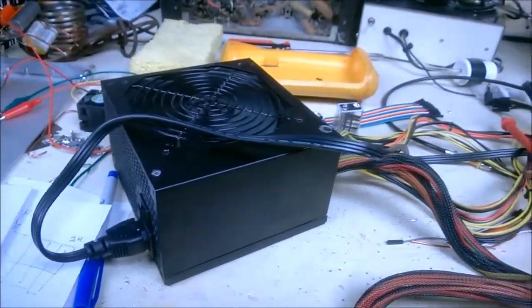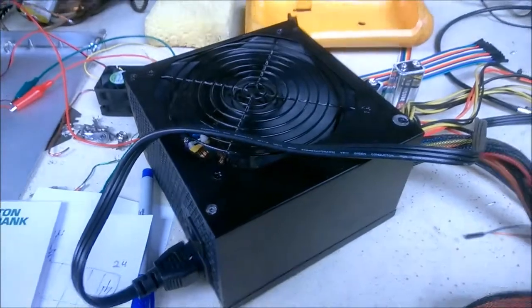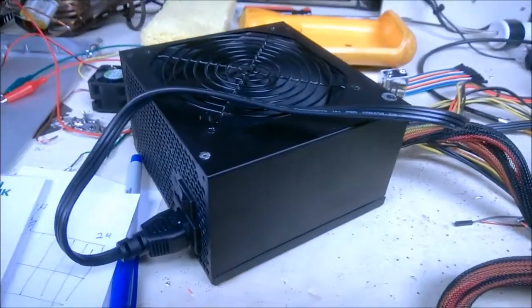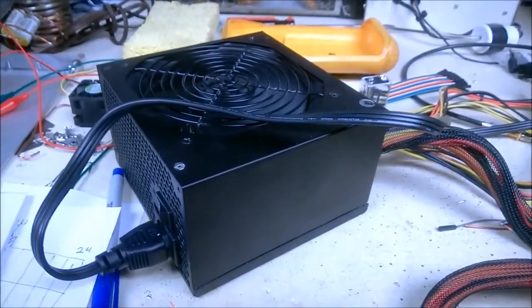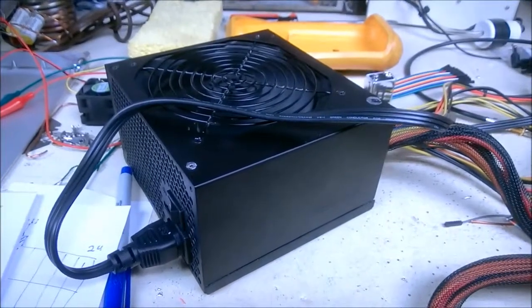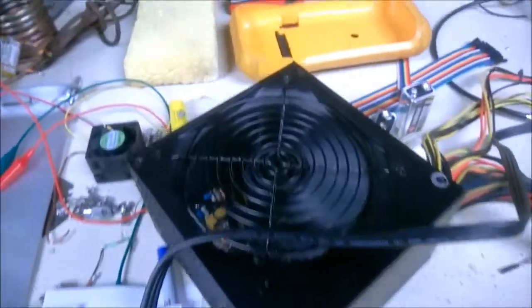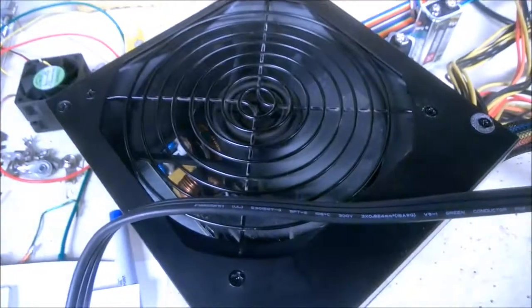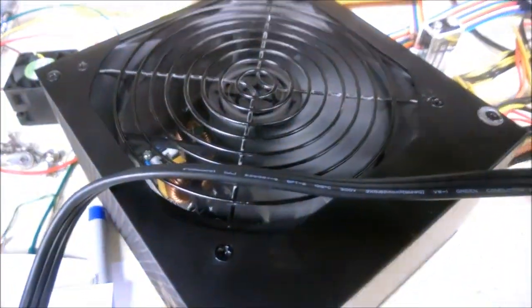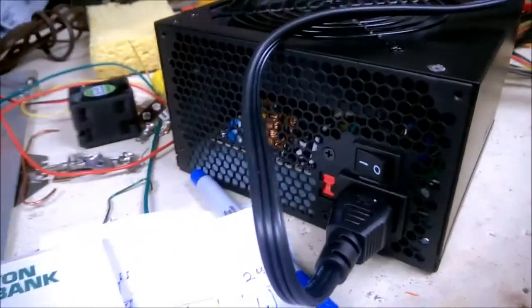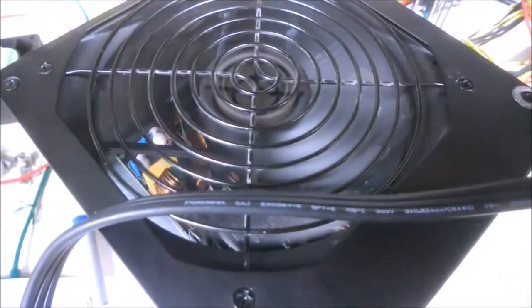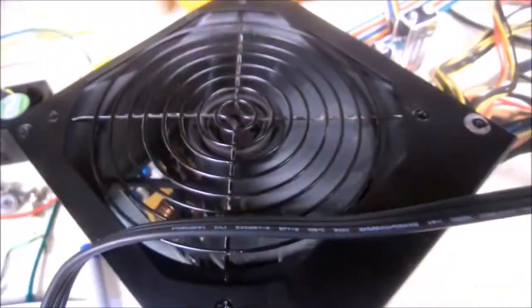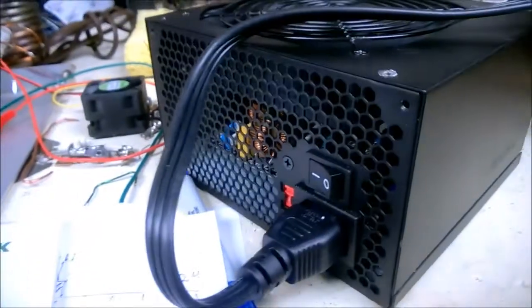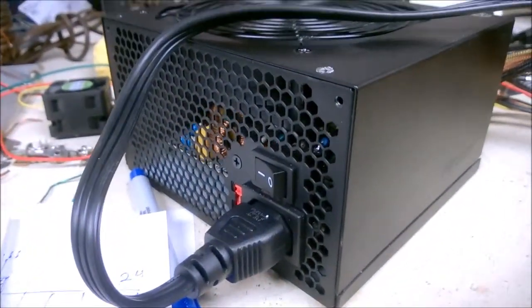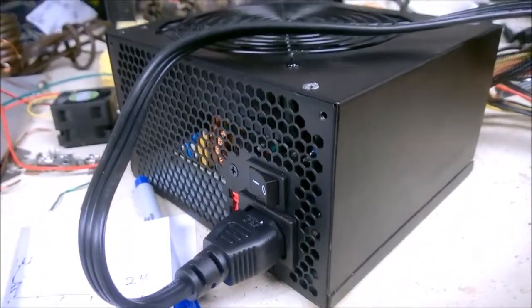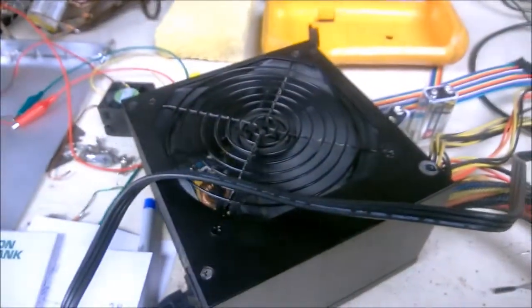A lot of the power supplies I've worked with before, and even this type of power supply, will have really weird regulation values, really off values, but what's really going on is that some component inside has either failed or is on the verge of failure. Typically power supply components are very high energy, meaning they produce a lot of heat, a lot of current, a lot of voltage, and a lot of power potential. So when a component fails, it can be pretty spectacular.